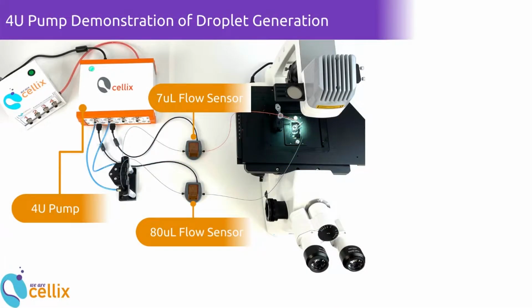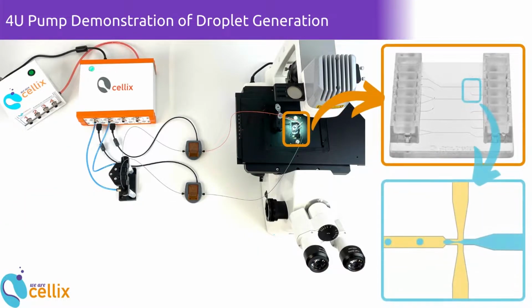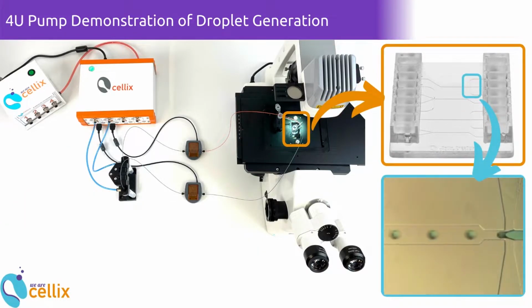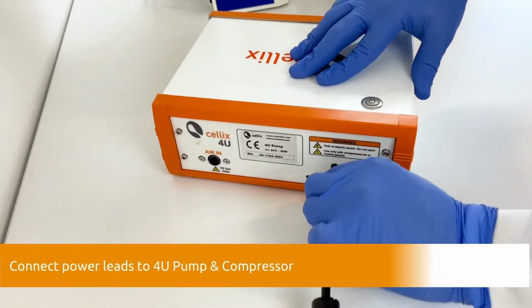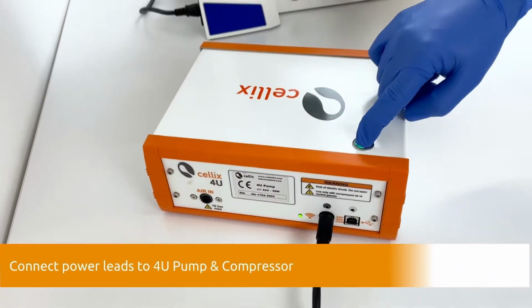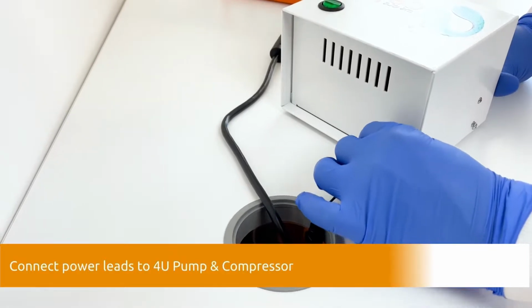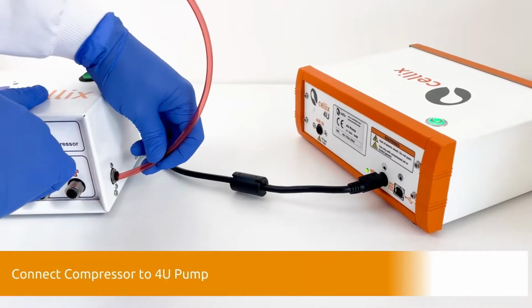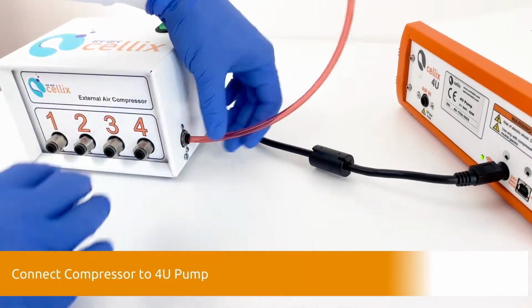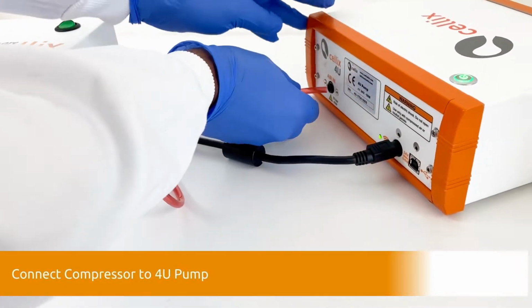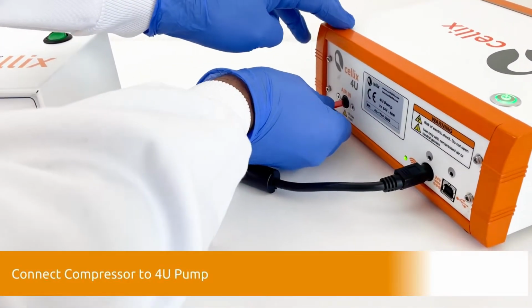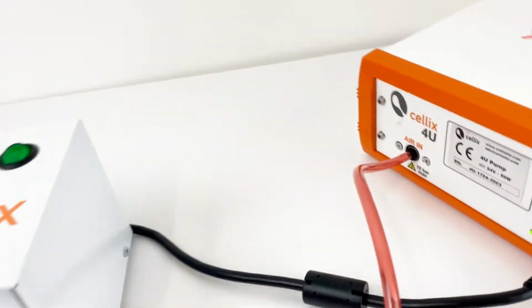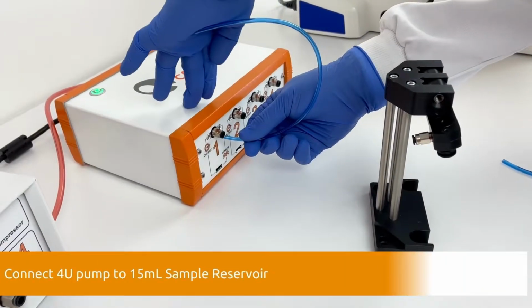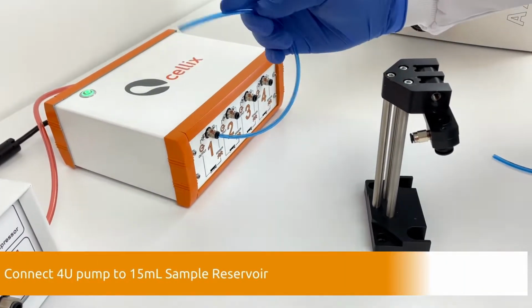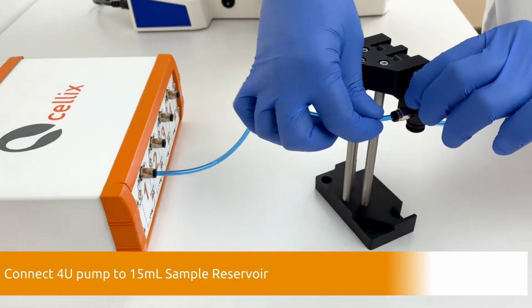This video will guide you through the setup and demonstration of Cellix's 4U pump for droplet generation of water and oil droplets. First, we must set everything up. To do this, connect the power leads to the 4U pump and to the compressor. Connect the compressor to the 4U pump via the red pneumatic tubing. Connect the 4U pump to the 15 ml sample reservoir via the blue pneumatic tubings.